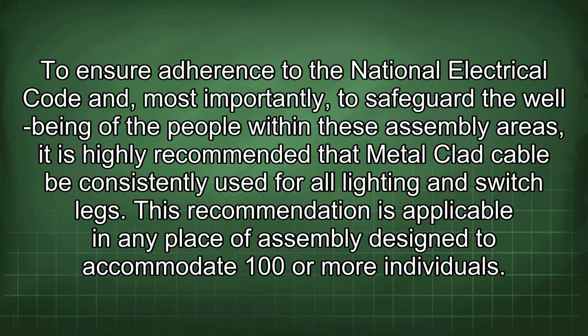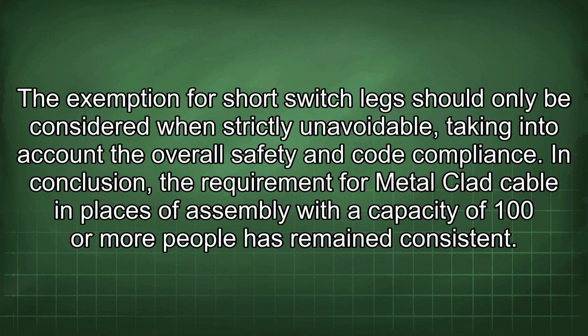To ensure adherence to the National Electrical Code and, most importantly, to safeguard the well-being of the people within these assembly areas, it is highly recommended that metal-clad cable be consistently used for all lighting and switch legs. This recommendation is applicable in any place of assembly designed to accommodate 100 or more individuals.